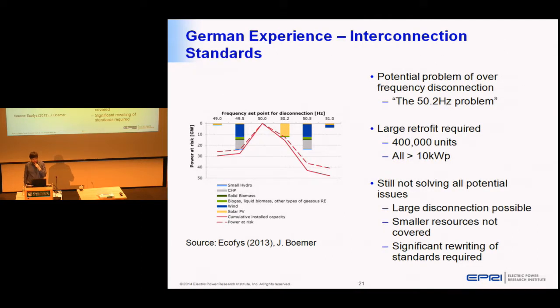Some of the other pieces are these interconnection standards, which address these problems. The German power system is a 50 hertz system, like the rest of Europe, but they've had this problem called 50.2 hertz—large frequency deviations to 50.2, 50.5, or 51 hertz can happen if a large amount of load is suddenly disconnected.